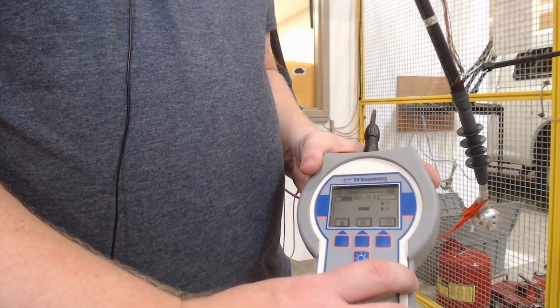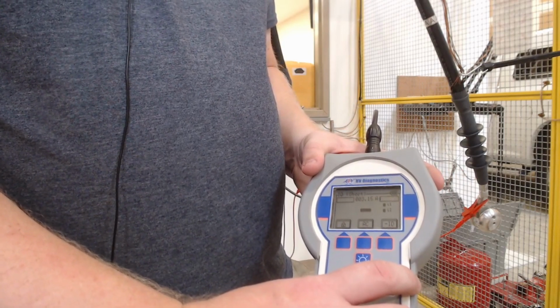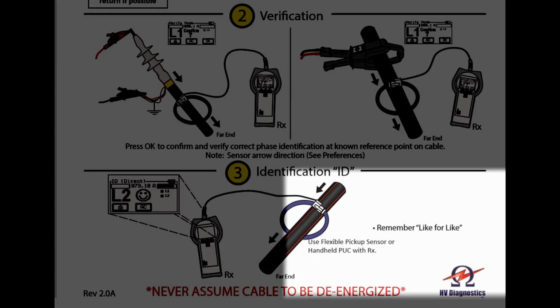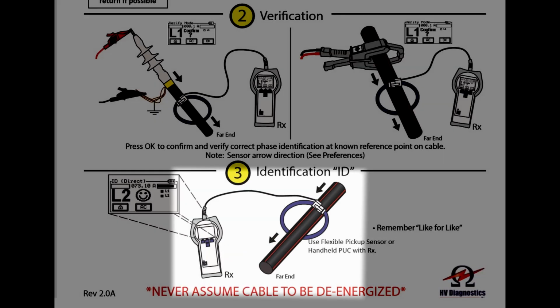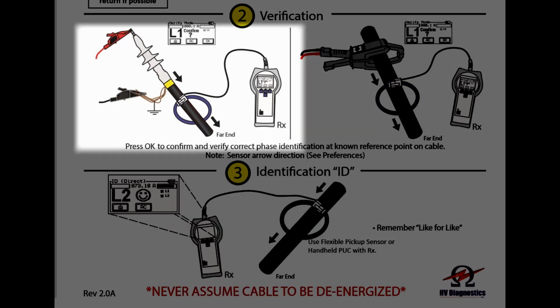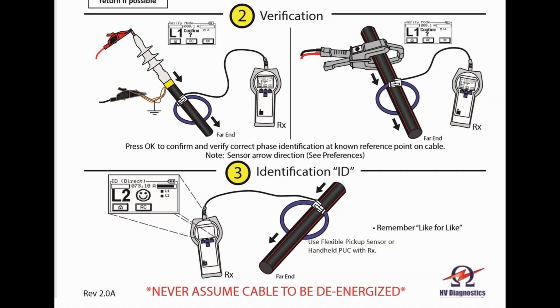We'll move upstairs and do the identification of the direct method next. Important note, before we move upstairs, when you verify or ID a cable, it needs to be performed in what we call a like for like. So if you are IDing around a shielded section in the middle of a cable, you also need to verify on a shielded section. Same goes for identifying on a non-shielded section, like a termination. Calibration and verification should be done on a non-shielded section as well.